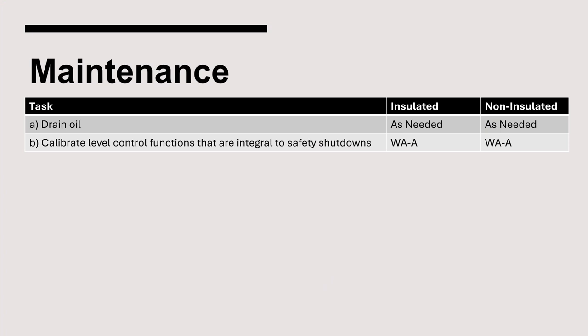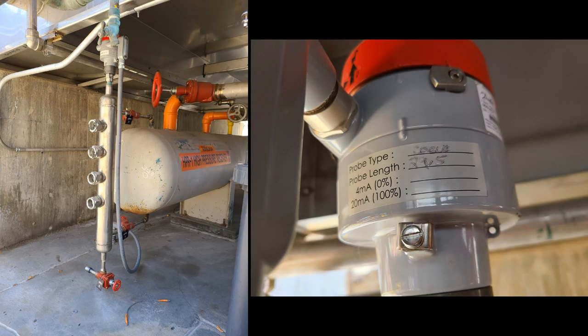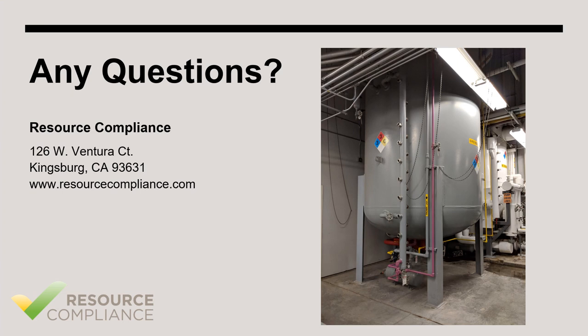IIAR 6 has two maintenance requirements for pressure vessels. First, oil must be drained as needed; oil typically collects in vessels on the low side of the system, so this is rarely required for high pressure receivers. The second requirement is to calibrate all level control functions that are integral to safety shutdowns where applicable — for example, if a level probe were interlocked to shut off liquid-injection cooled compressors if the level dropped too low, the calibration requirement would apply. This concludes our video on high pressure receivers. We have more videos on our channel about ammonia refrigeration and process safety management — feel free to check them out if you are interested.